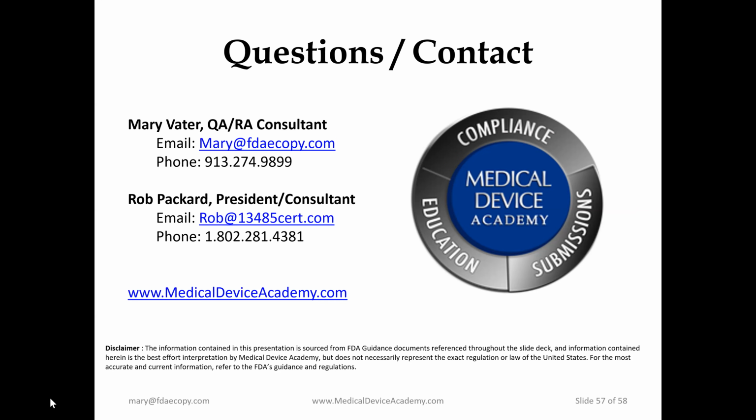Is human factors testing still required for a special 510K to an existing device? First of all, for those people that don't know what a special 510K is, you can only submit a special 510K if you already have a 510K for a device and you're making a minor modification to that device. If it's a major modification, then you can't do a special; you have to do a traditional or abbreviated. The real attractive feature of a special is a 30-day review time clock with the FDA instead of 90 days.